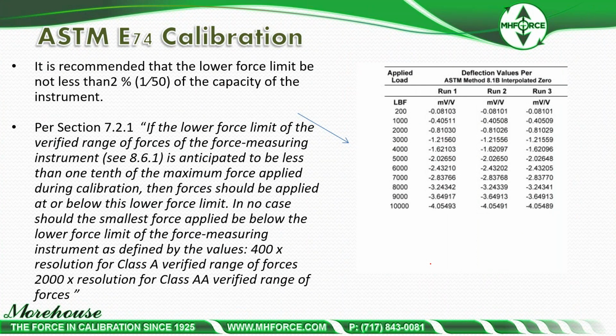And then it is recommended that the lower force limit be not less than 2%, 1/50th of the capacity of the instrument. Here's the 10,000 pound load cell looking at the first point, that's 2%. Per 7.2.1, this is what I've been talking about. If the lower force limit of the verified range of forces of the force measuring instrument is anticipated to be less than 1/10 of the maximum force applied during calibration, then forces should be applied at or below this lower force limit. In no case should the smallest force applied be below the lower limit of the force measuring instrument as defined by 400 times the resolution for Class A and 2000 for Class AA.